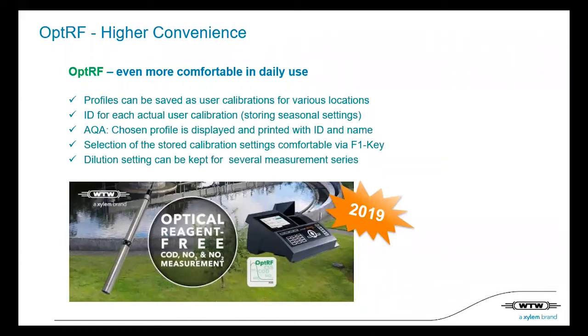So we can store profiles. For example, if you have 3 basins in your sewage plant, you can store all the user calibrations for each individual basin. You can give it an ID and a name. This will be output together with the calibration settings, and you can see dilution settings, for example, at each measurement. You can also store dilution settings in different measurement series. So there is a lot of convenience. We introduced this in 2019.